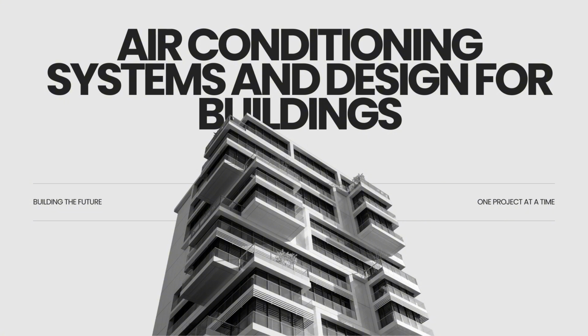Absolutely. Our source details 4 common types of split-type indoor units, or FCUs, each designed to suit different architectural aesthetics, air distribution needs, and spatial requirements. It gives designers a really wide palette of options. First, we have the wall-mounted type. This is probably the most common one you'd see in residential settings or smaller offices. It's mounted high on a wall, typically near the ceiling. They're relatively easy to install compared to other FCU types and are fairly visually discreet. Okay, the standard high wall unit.